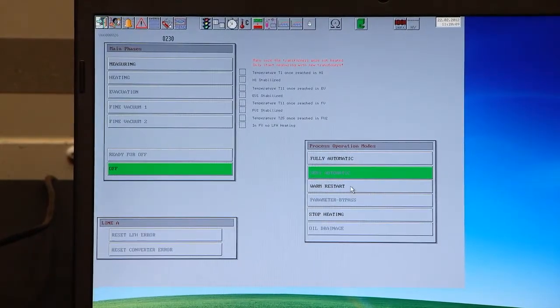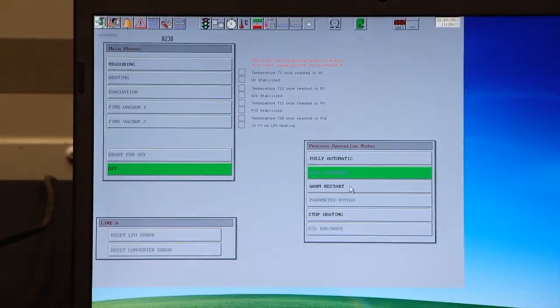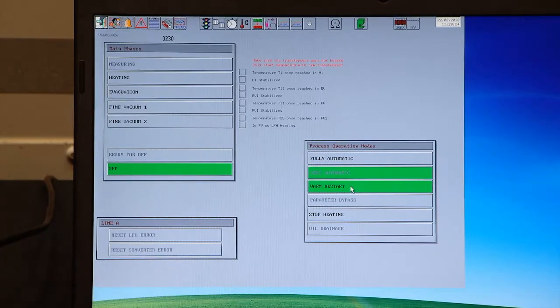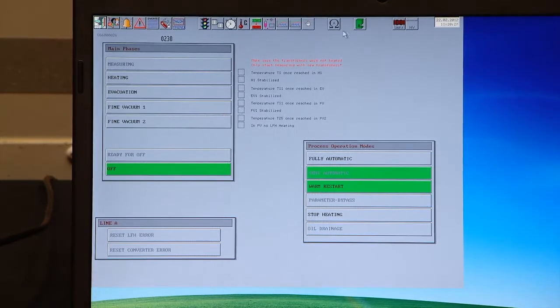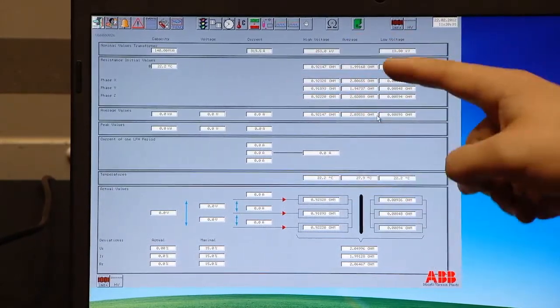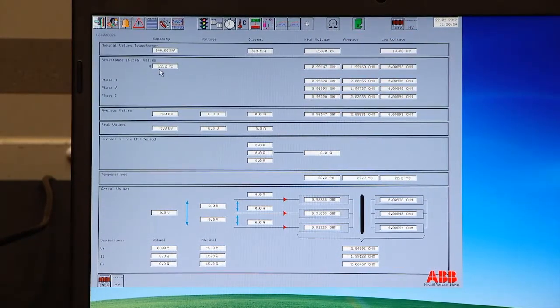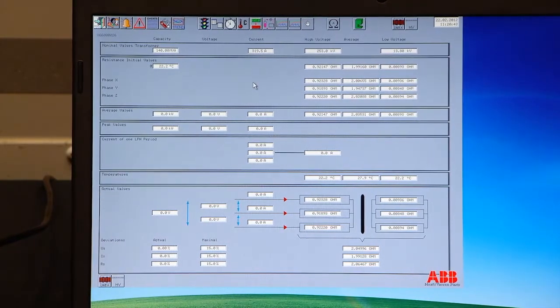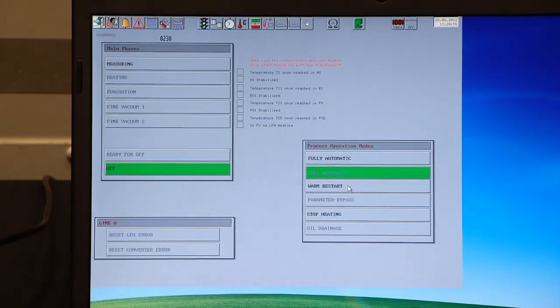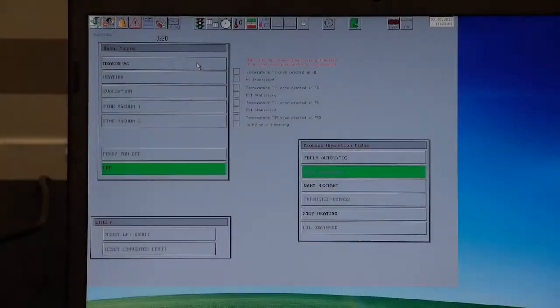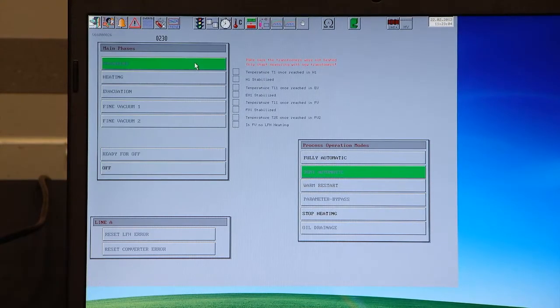Warm restart, I have not mentioned it before, but if you have done a measurement, you have the initial measurement, you have it matched to your temperature, you can start again using that initial temperature again. So we can click warm restart because yesterday we made our resistance measurement. They are still available on this page, we still have them here. The resistance readings, we have them matched to our 22.2 degrees. This has not changed, it's the same transformer, same connections, everything is the same. So it's not necessary to do the measurement again. You can click warm restart and we can go to heating directly. We're ready to go for measurement, measuring, click on it.